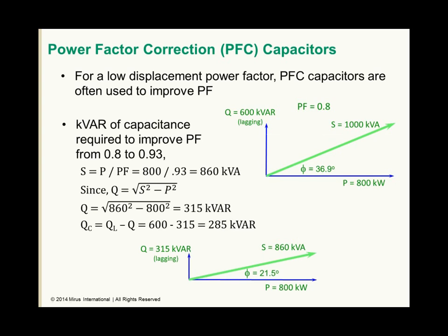So if we want to improve the power factor, say the utility has a minimum power factor of 0.9. We want to improve it to a safe level, so we've chosen 0.93 as our design level. Then the resultant apparent power would be the 800 kilowatts divided by 0.93, so it needs to be 860 kVA.